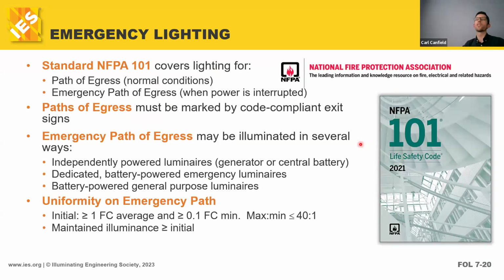Some other codes here. Emergency lighting, again, our friends, the NFPA. NFPA 101. This is another major code that engineers and electricians and architects and designers need to adhere to. This is life safety code. So in terms of the lighting world, lighting is a big one for life safety. Lighting is what gets people out of the building in case of an emergency, right? There are terms like the path of egress, which is kind of what it sounds like. It is a designed, a specified, and a dictated path from each and every space in that building to get out, basically get into the path of egress, get into the corridor, get into the nearest stairwell, get out the nearest exit door safely. That path has illumination requirements around it, right?